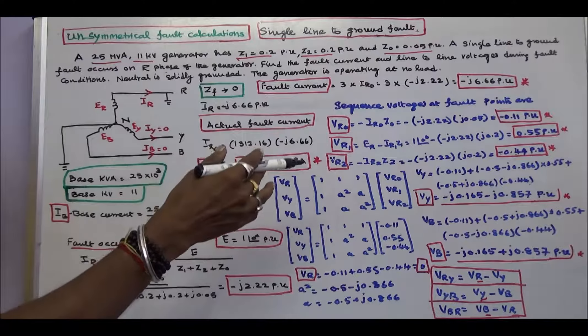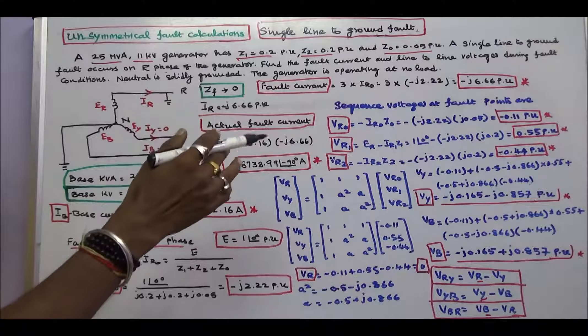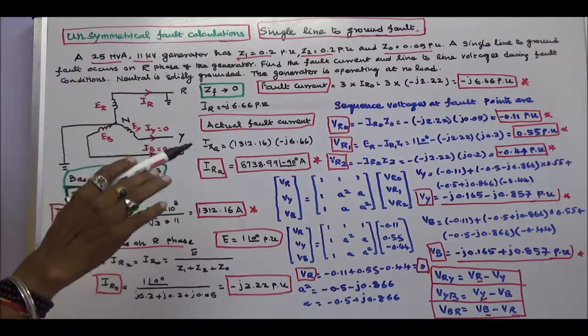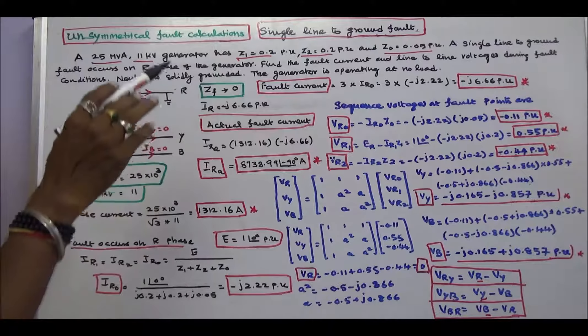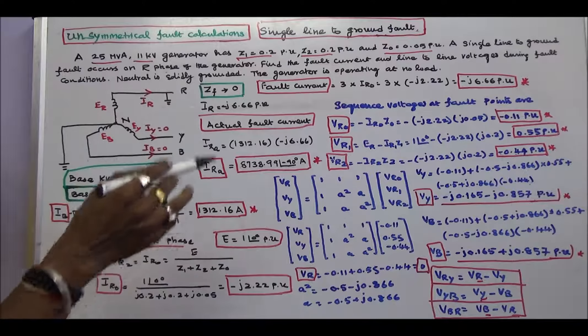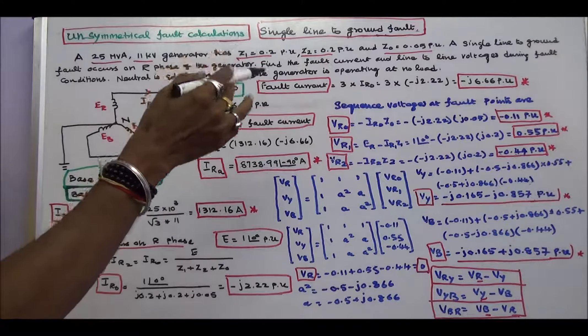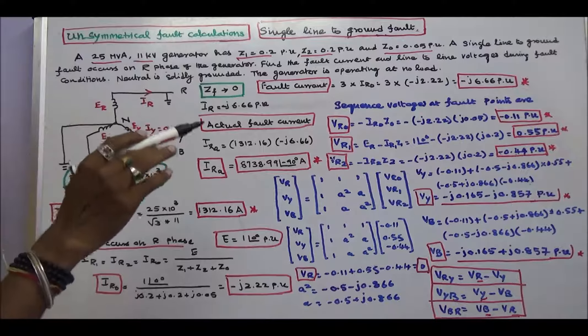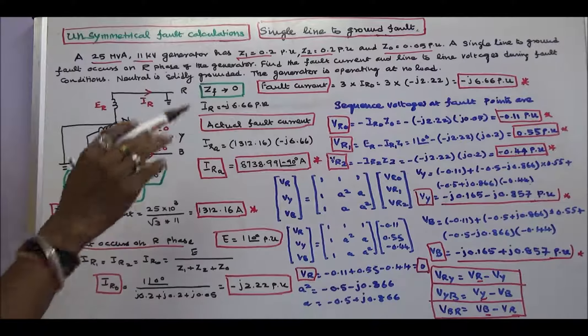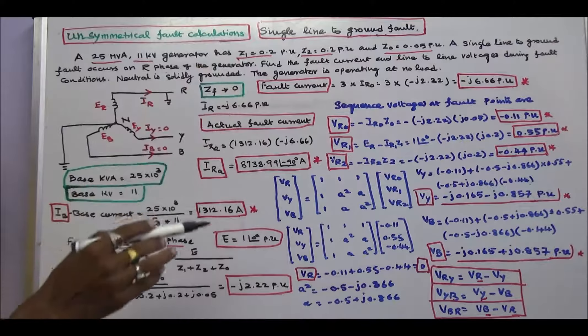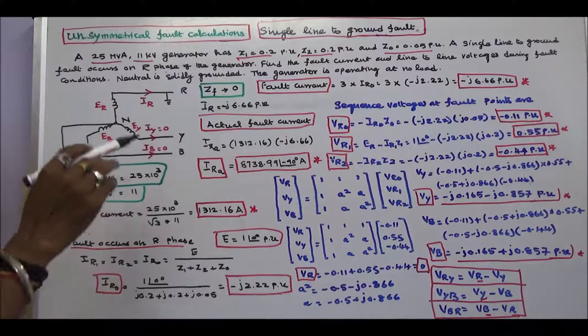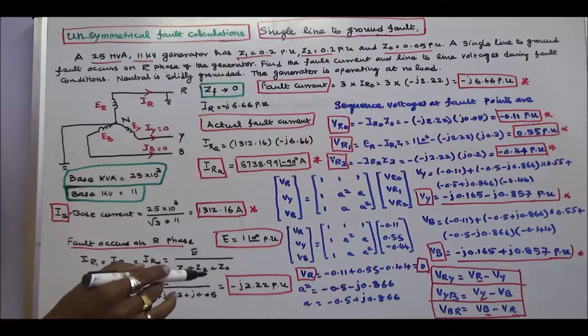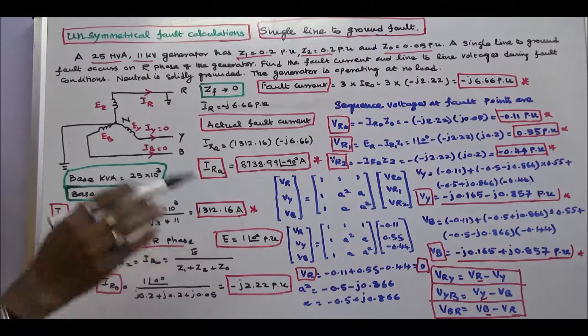This class we work out one problem. A 25 MVA, 11 KV generator has positive sequence impedance Z1 equal to 0.2 per unit, negative sequence impedance Z2 equal to 0.2 per unit, and zero sequence impedance Z0 equal to 0.05 per unit. A single line-to-ground fault occurs on R phase of the generator. Find the fault current and line-to-line voltages during the fault condition. The neutral is solidly grounded, meaning fault impedance ZF equals 0, and the generator is operating at no load.